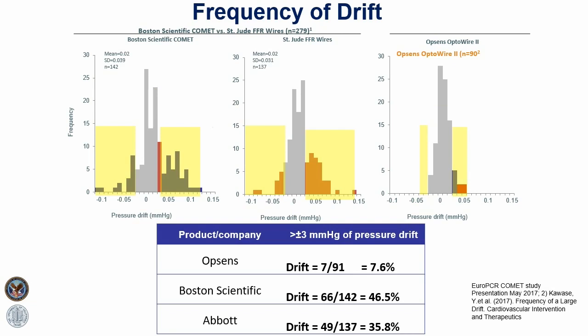This was again demonstrated earlier. When you compare these from the data provided to us, you can see that the optical sensor wire from OpSens was superior with lesser drift. I like that. Now, is there zero drift? No, there is never 100% zero drift, but 90% of your cases or more will have no drift, and 7.6% in this study would have a little drift. But you have much more drift with the other wires.